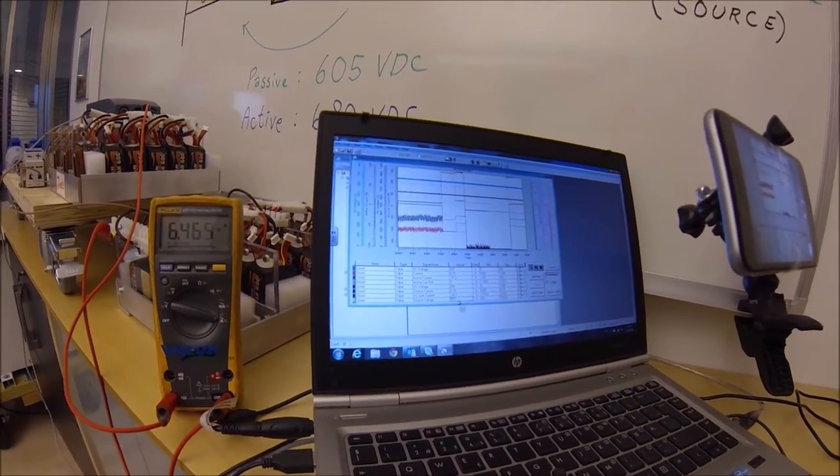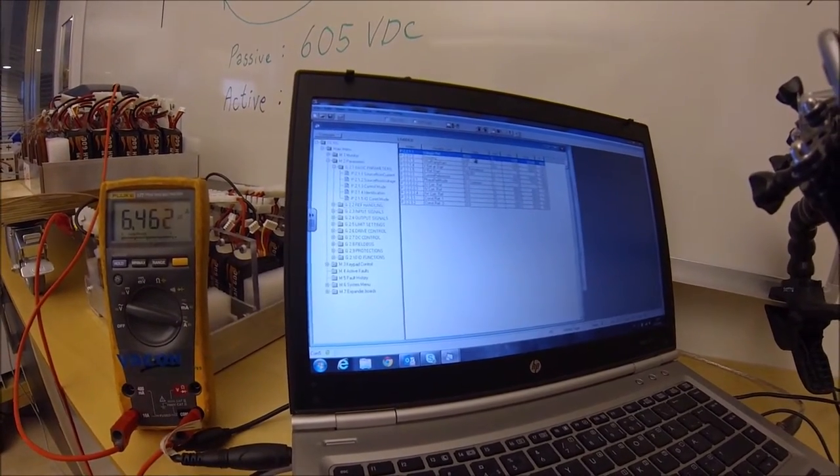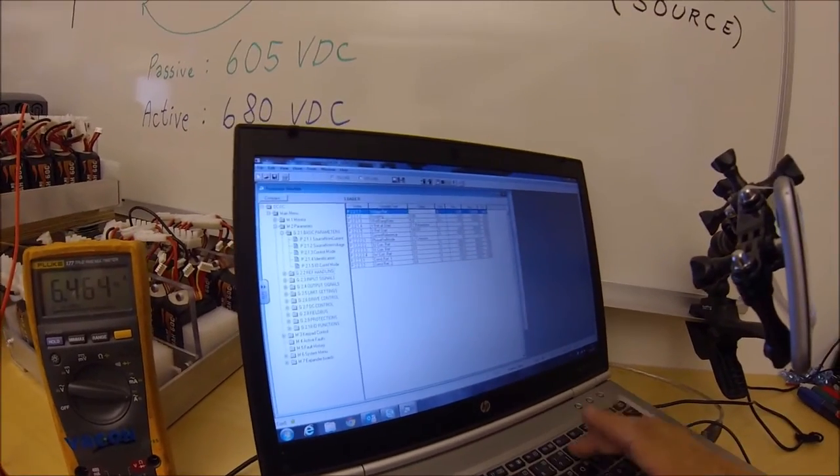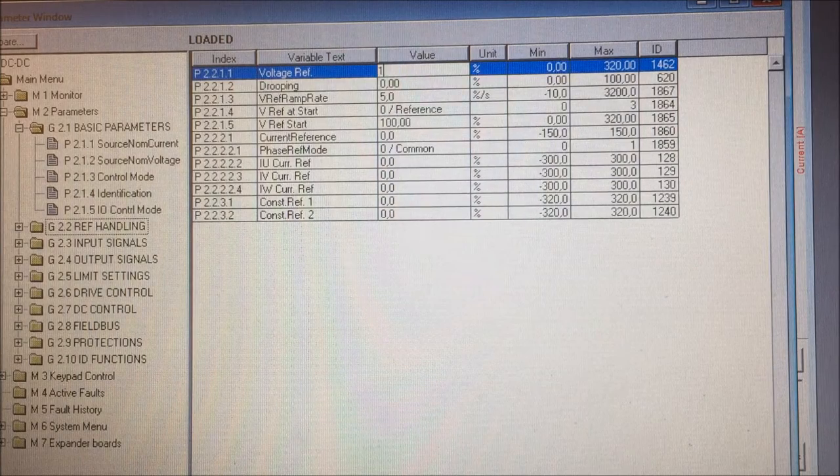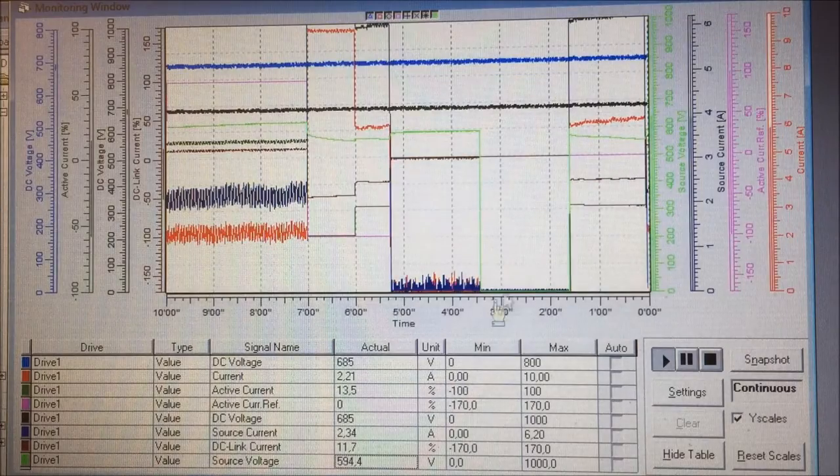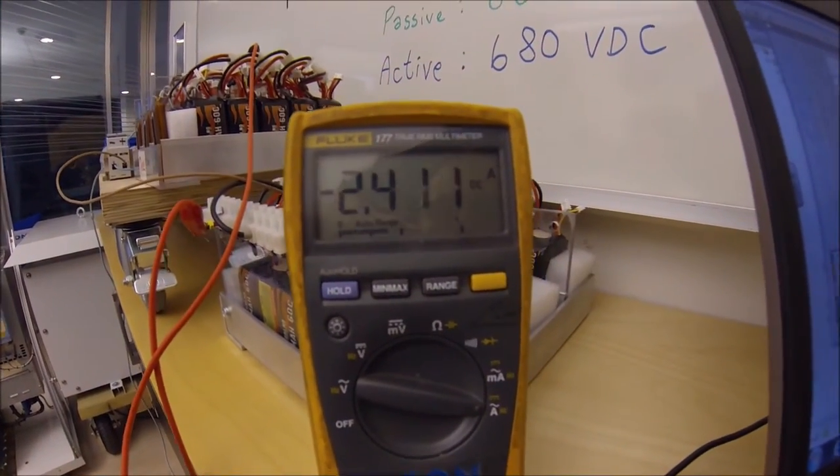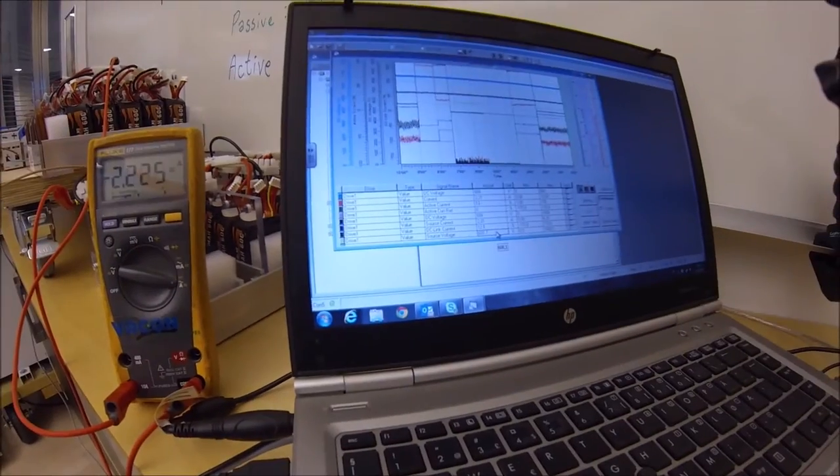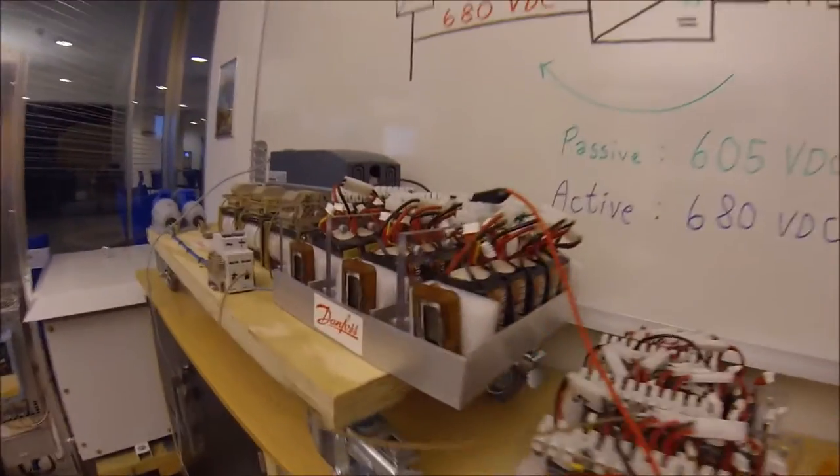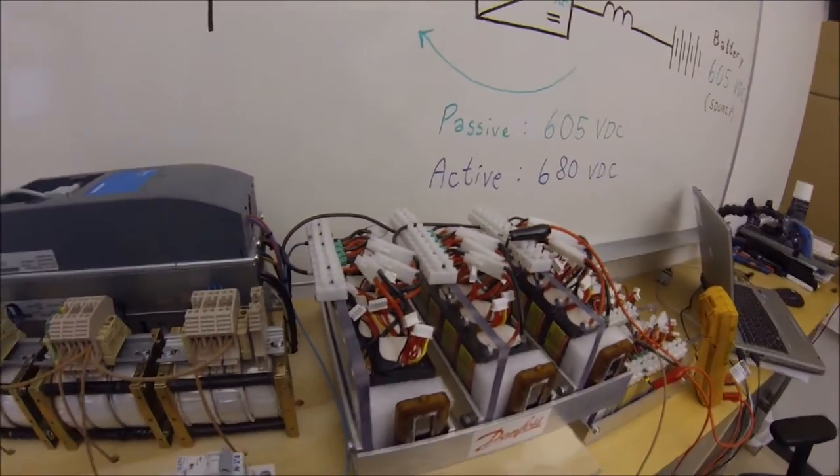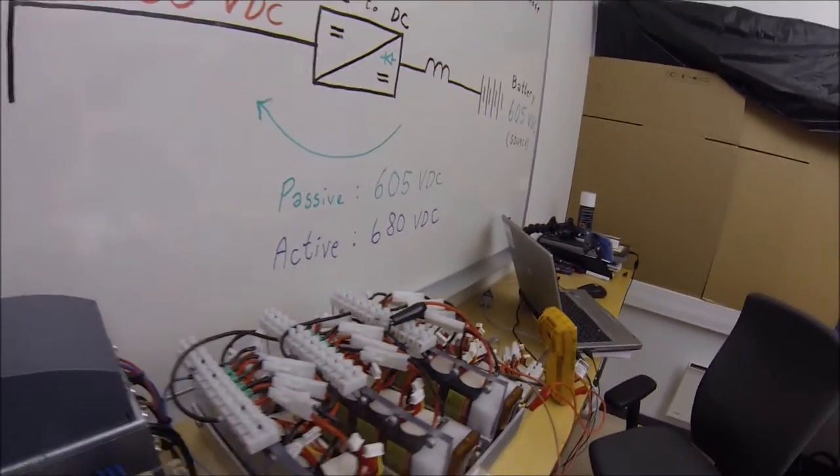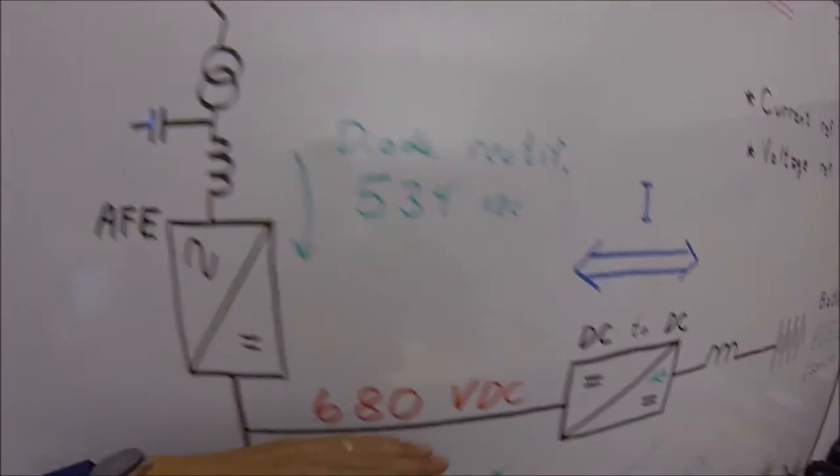Okay, now the voltage has dropped quite a bit. So I want to change direction of the current. So if I aim for, let's say, 105%. The current should go then in opposite direction. The minus on my fluke shows that I am charging my battery. The voltage has increased. The drive tried to increase the voltage here on the source side. And the current is flowing in this direction. So we are basically taking energy from the city and going into this direction. And we are doing it now in a voltage reference mode.